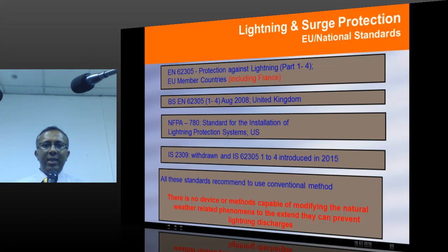So about the standards in other parts of the world, a lot of our installations are with early streamer emission devices, and the suppliers always claim that it conforms to the national French standard. You have to understand that this particular NFC code is not the main standard. It is a supplement to the original standard, and even in France, the standard is NF EN 62305. Whatever I explained here is the French standard. Early streamer emission is an added subject, an added standard. Only the air terminal is considered, but under several conditions.